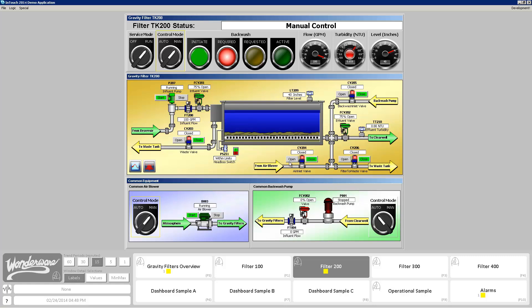Other things that can happen are distracting elements. I'm going to open the air blower and the air inlet valve on here to show how in this demo there were a lot of bubbles indicating air going through the system. Is that a problem? What we find is that when people are looking at the screen, they're just looking at the bubbles because that movement is extremely distracting. When you do things like spinning pumps, movement, or blinking when things don't require action, you are distracting your operator and reducing their situational awareness.